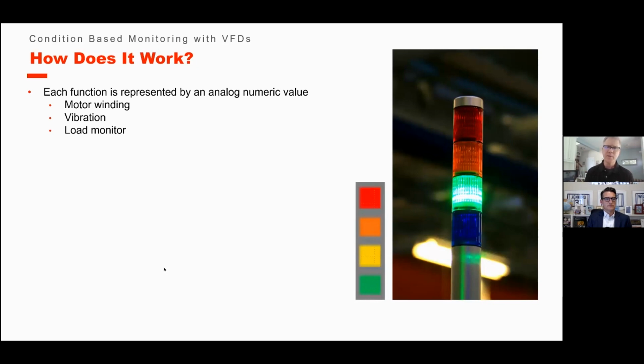So as you set up your baseline and your alarms and warnings, that's all a numerical value inside the software. You're looking for the motor winding integrity, actually. You're looking for vibration, which is an external sensor feed. We'll talk more about that. And we're looking at the actual load envelope of how that motor is being loaded. And that's a view of how the machine is acting as well.